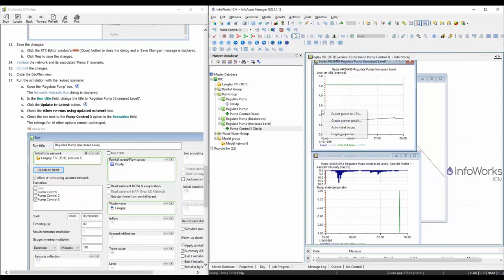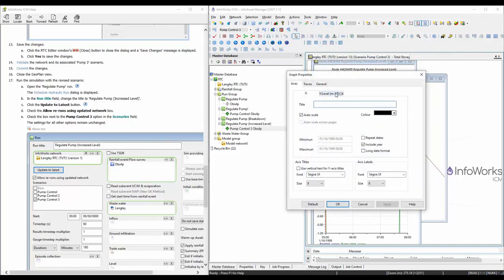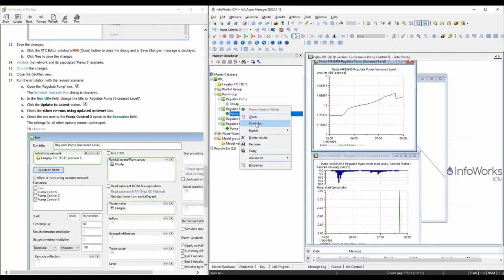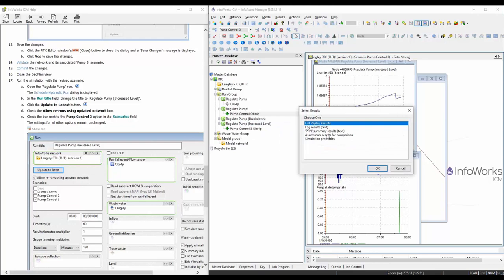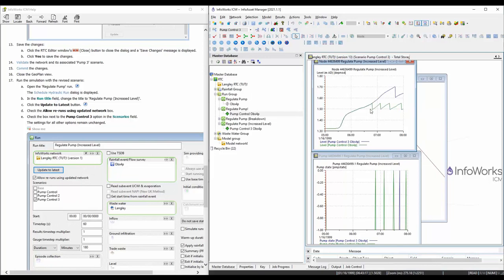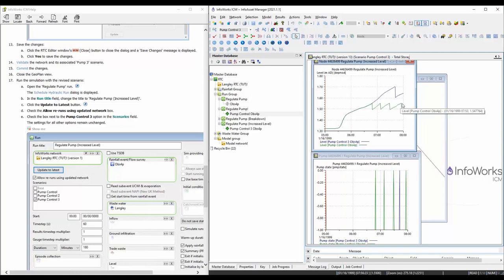Let's limit the range to 1 to 2. You can see the pump only turns on once. Let's compare that with the original setup using open as alternative results for comparison. Now you can see the overlay — the green one is the original. Because we increased the level, it keeps going up until 1.7 before it starts to pump, whereas before it was 1.55. Once it reaches 1.55 it starts to pump and lowers to 1.5, stops pumping, and just keeps doing this. You can show everything here. That concludes this tutorial — I'll see you next time.